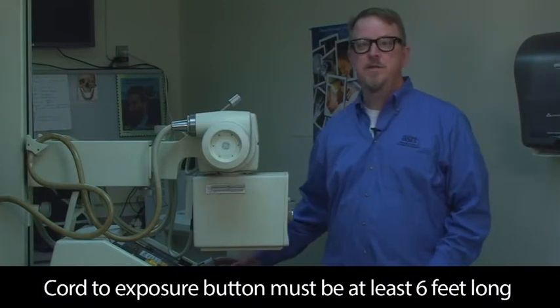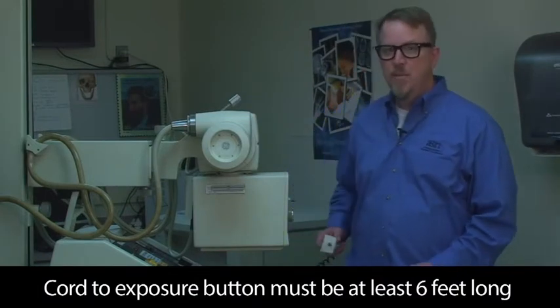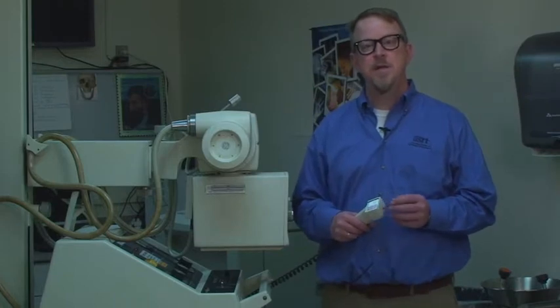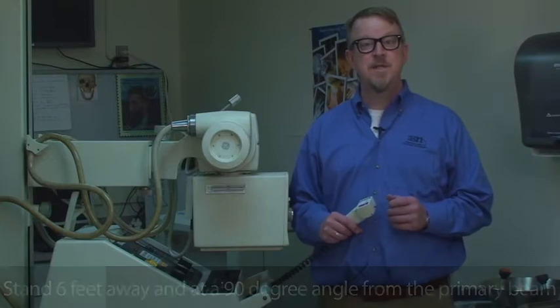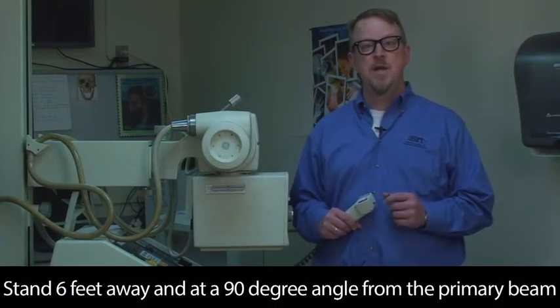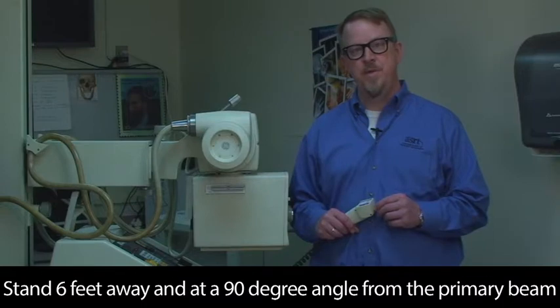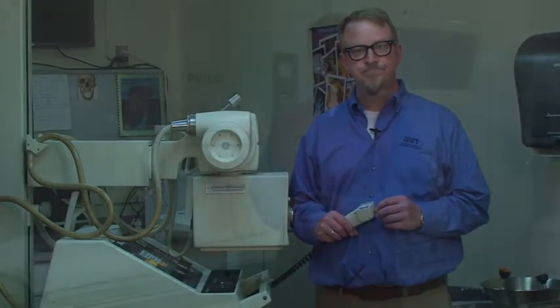The technical factors used in portable imaging may be slightly lower than a fixed machine, but the technologist generally doesn't have an opportunity to leave the room and take the exposure remotely. To ensure the technologist's safety, the cord to the exposure button on a portable machine must be at least 6 feet long. Each portable X-ray machine should have a hook or storage place for a lead apron, which technologists should wear when performing portable exams. Additionally, the technologist should stand at least 6 feet away from the patient and at a 90-degree angle from the primary beam, where there is the least amount of scatter.